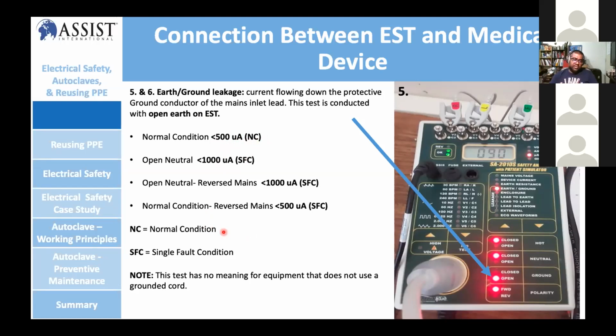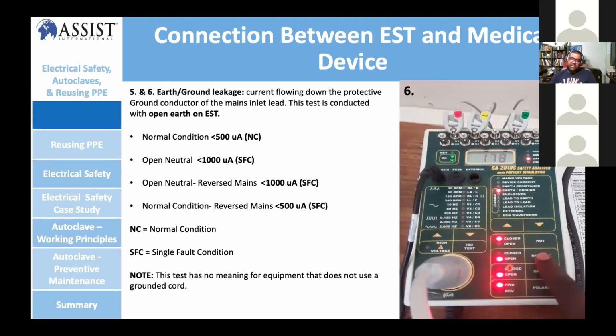So for the single fault, when you say open neutral, you're going to do a simulation on the electrical safety tester by pressing the switch on the device. You're going to open up the neutral line, and when you open up the neutral line, you're going to get a reading somewhere around 178, something like that. So it's going to increase the reading because your neutral is open and your earth is open. The leakage current is looking for a different path. So this is how you do the testing.